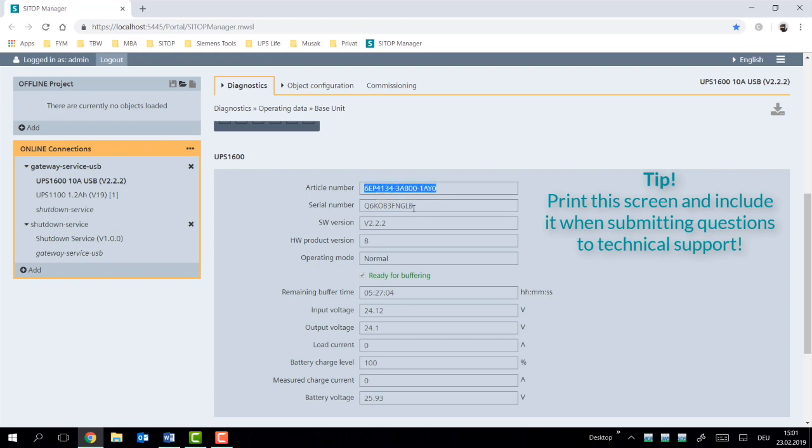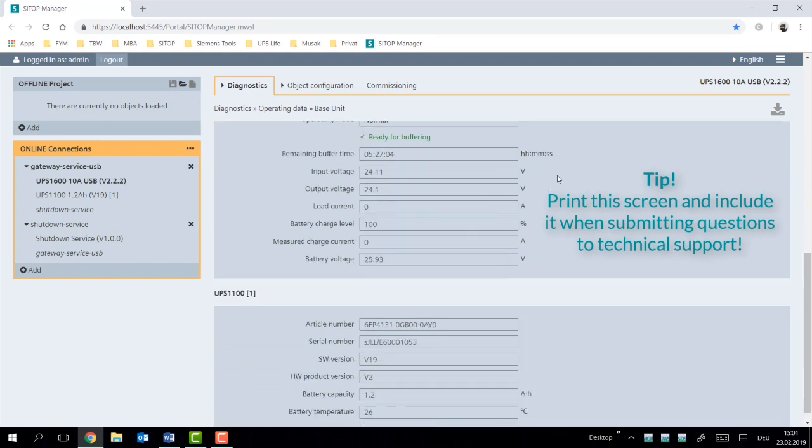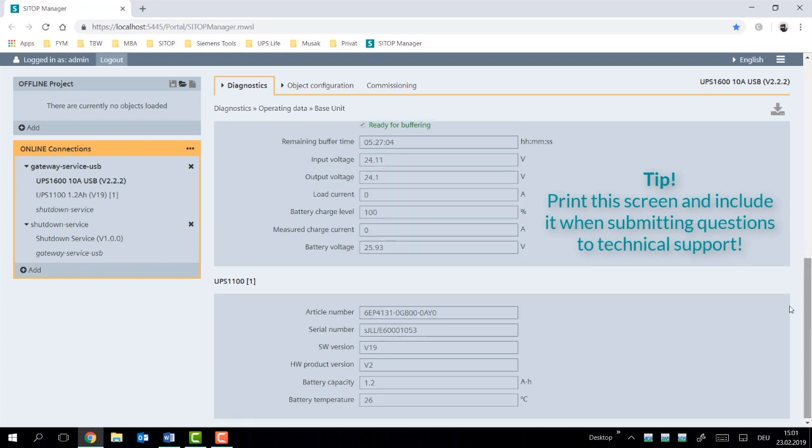We have the MLFB, we have the exact serial number, we have the software and hardware version, we have the current mode that it's running in, the ability to buffer, and then a number of different points: input and output voltage, battery charge level, and of course for each individual battery also the important data points.